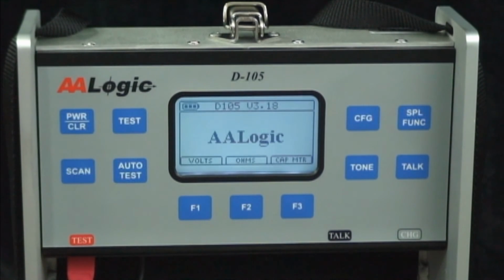This has been an overview of the D-105 AALogic test set. This test set contains most of the test features that are normally used when identifying cable faults and troubleshooting cable pairs. It also includes the talk battery used to establish communications, a tone feature for identifying cable pairs, and also a probe function, allowing the user to use this in almost every application.